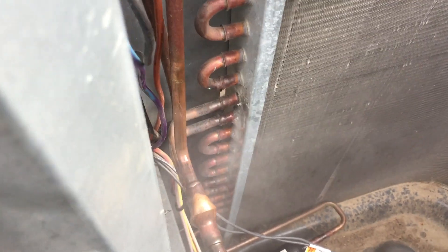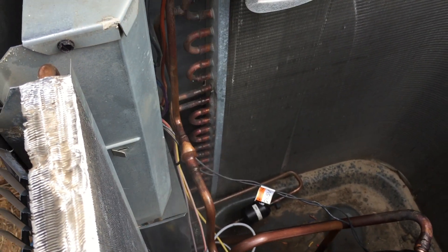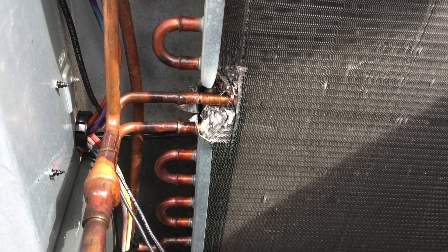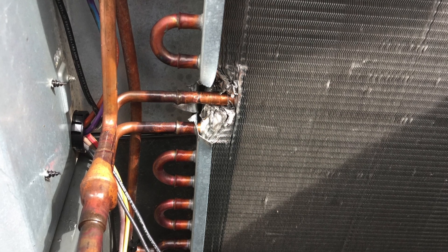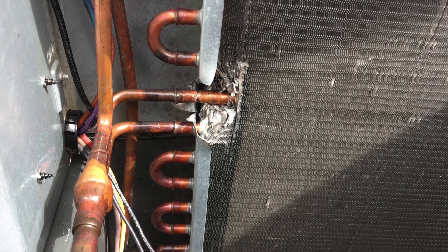In this case I repaired the coil and I'll tell you why. I'll show you some pictures of the repair. In this series of pictures you can see I pulled some of the fins off so that I could get in there to repair this. I've done this repair before and I've had various people say that I was damaging the coil or there was not enough heat transfer.